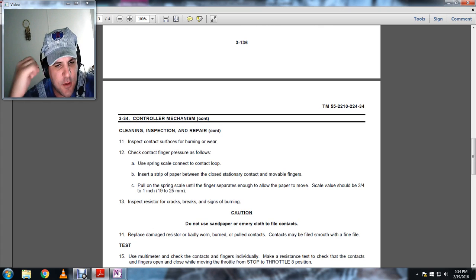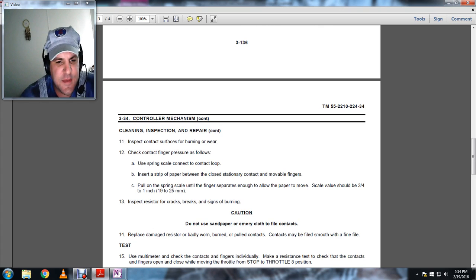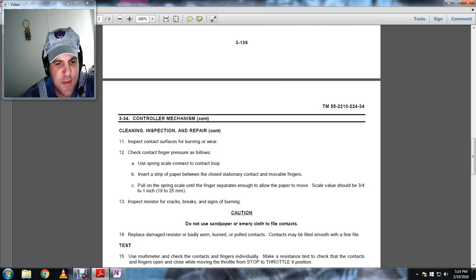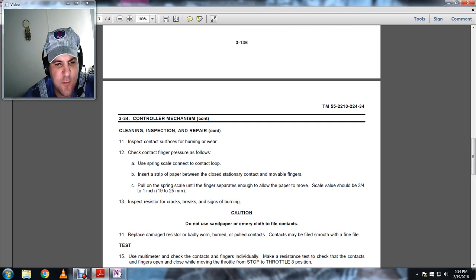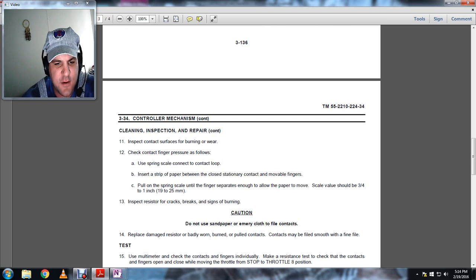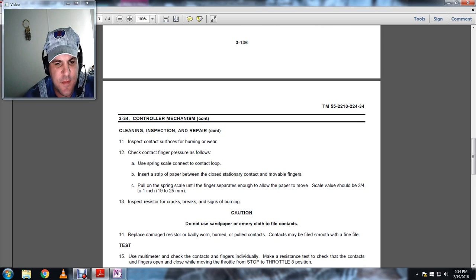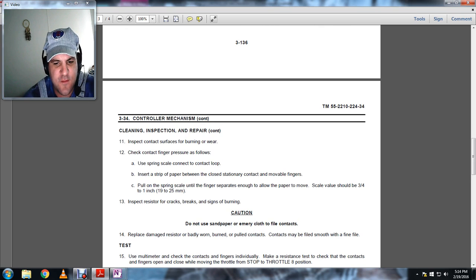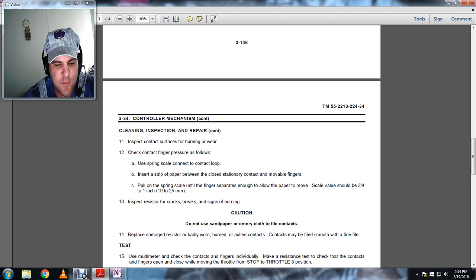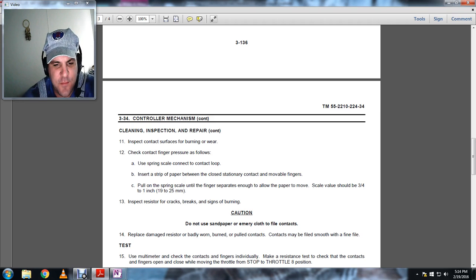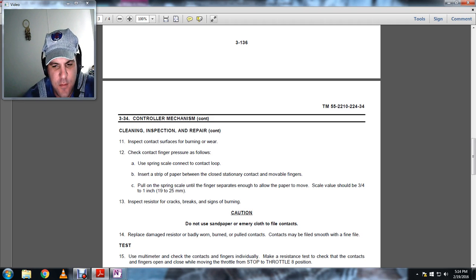Cleaning and inspection, repair continued. Eleven: inspect the contact surfaces for burning and wear. Check the contact fingers pressure as follows. Use a spring scale. Connect the contact to the loop and insert a strip of paper between the closed stationary contact and movable fingers. Pull on the spring scale until the finger separates enough to allow the paper to slide or move. Scale value should be three-quarters of an inch to one inch, or 19 to 25 millimeters.